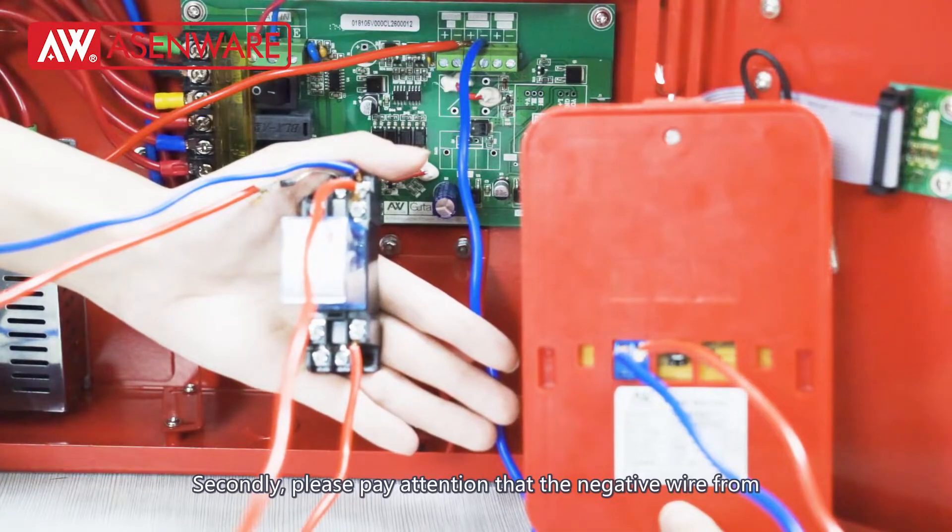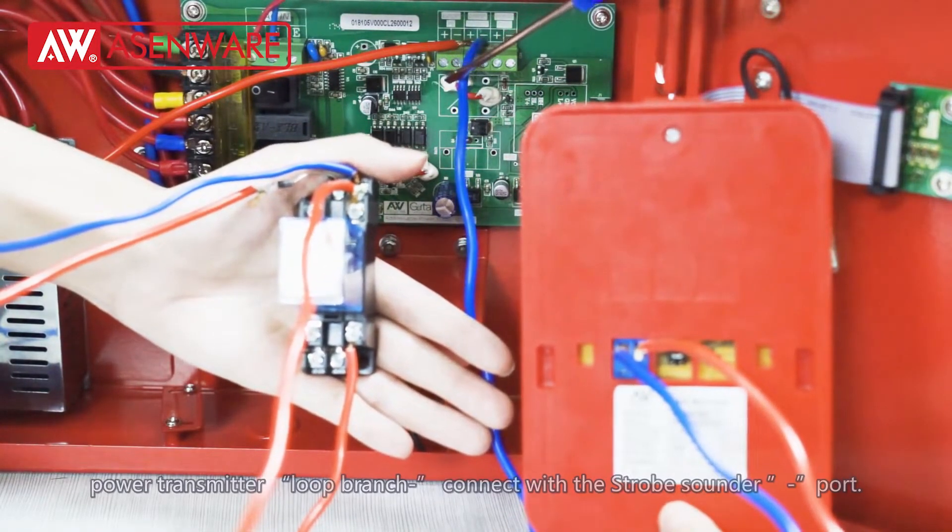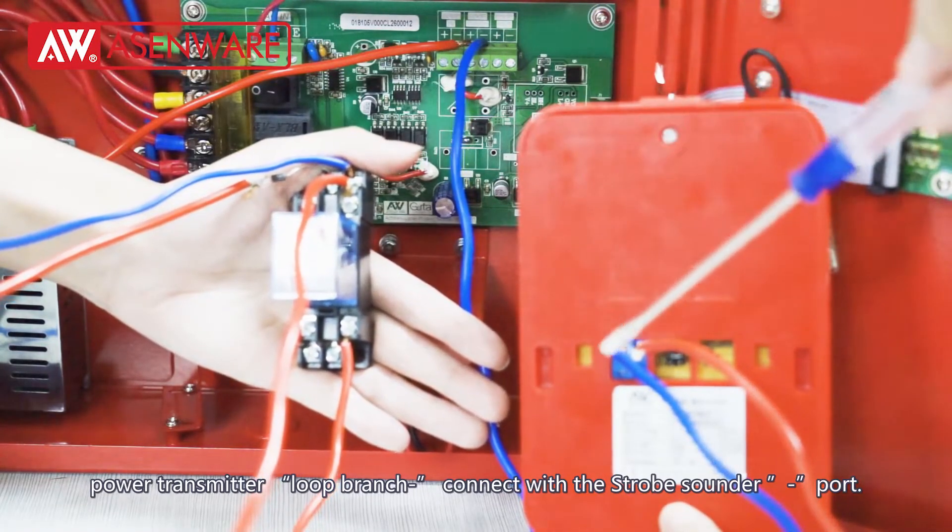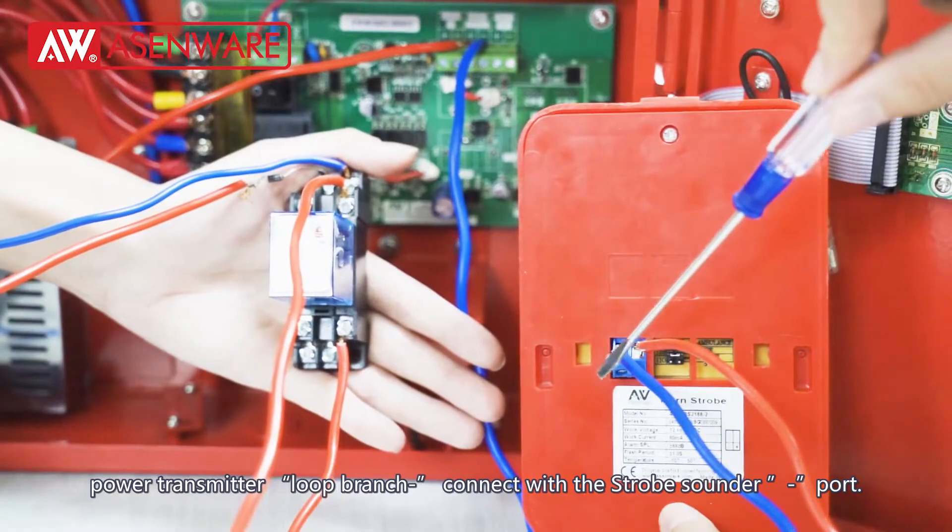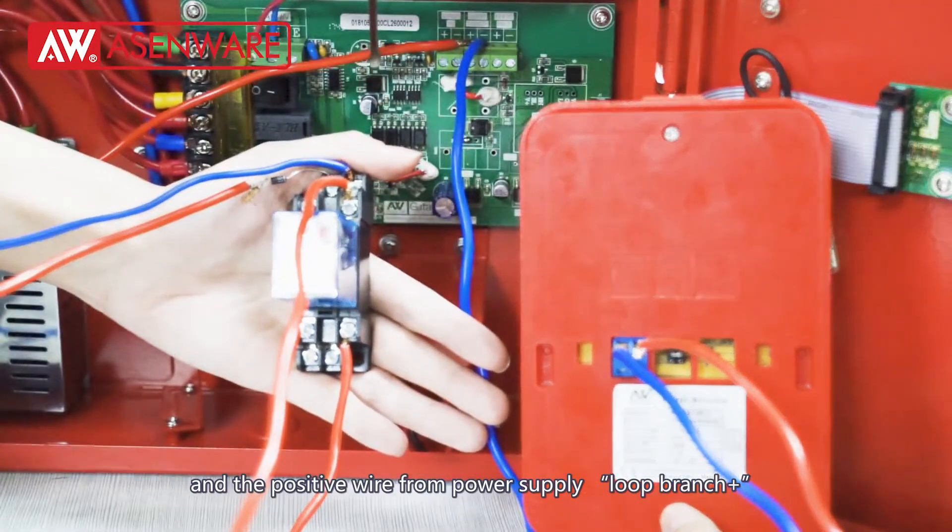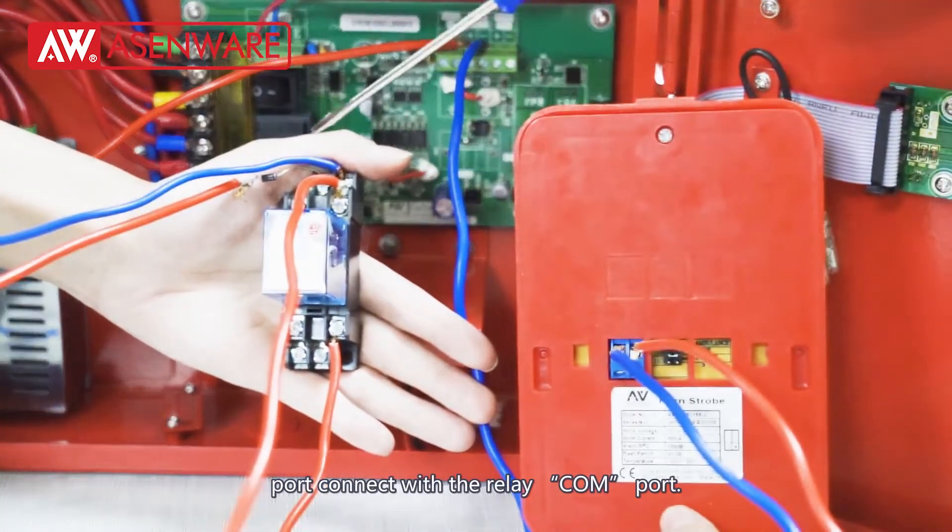Secondly, please pay attention that the negative wire from the power transmitter loop branch negative port connects with the strobe sounder negative port, and the positive wire from the power supply loop branch positive port connects with the relay's common port.